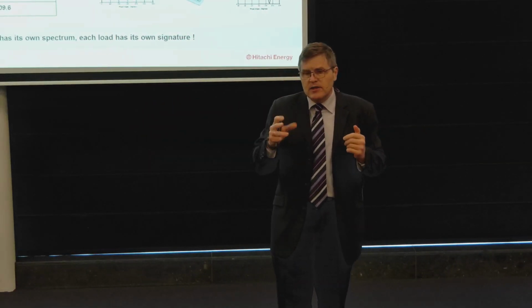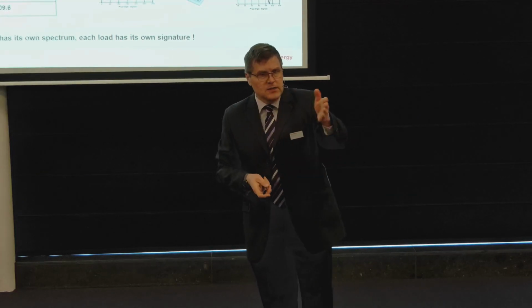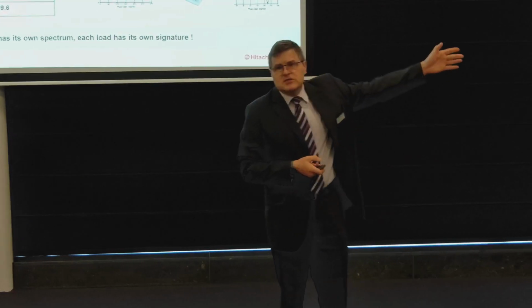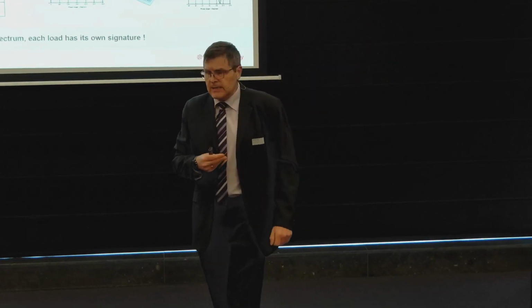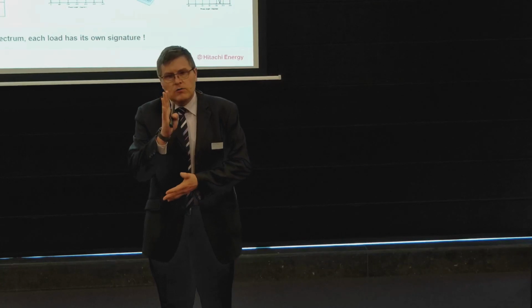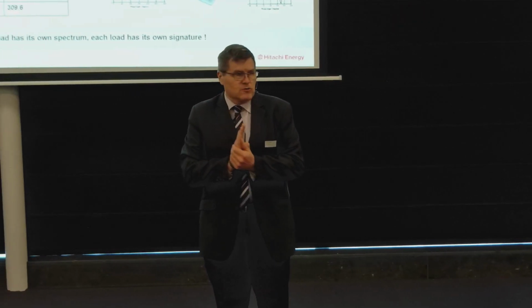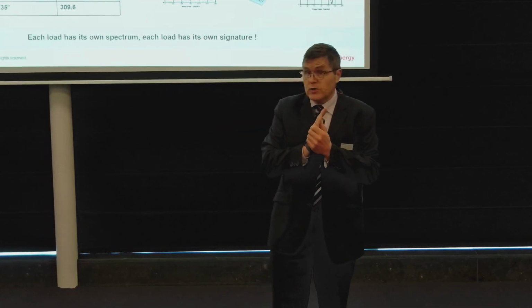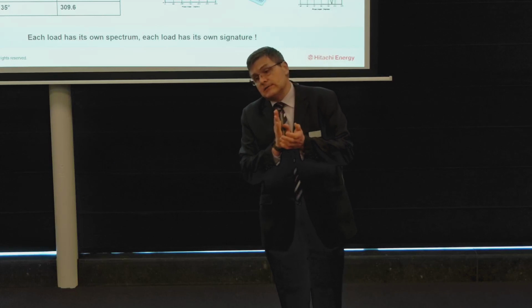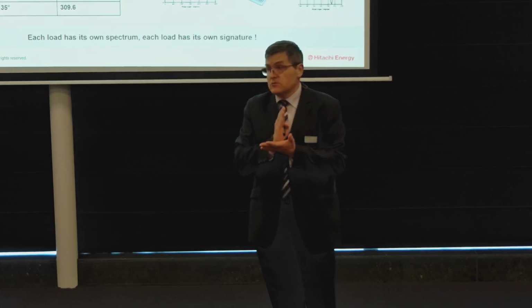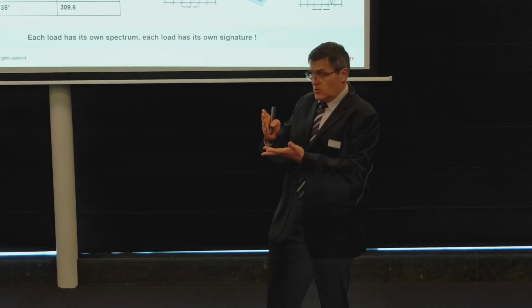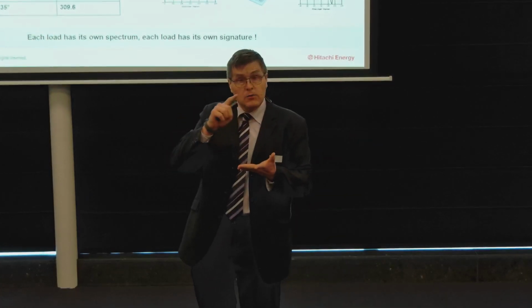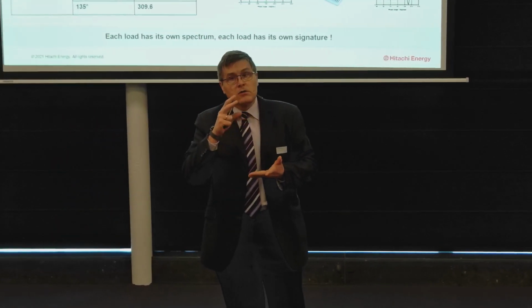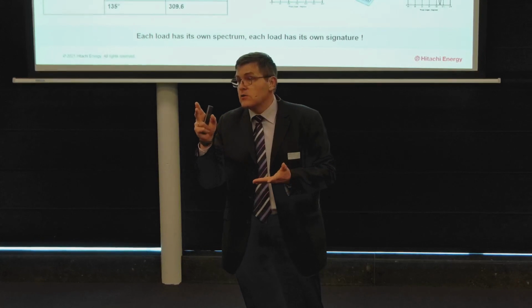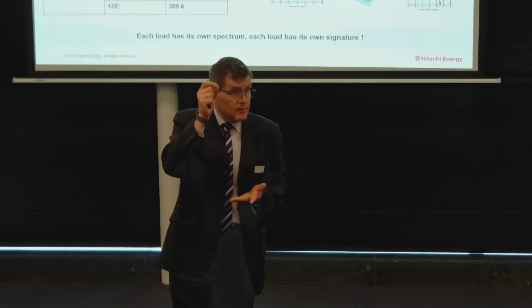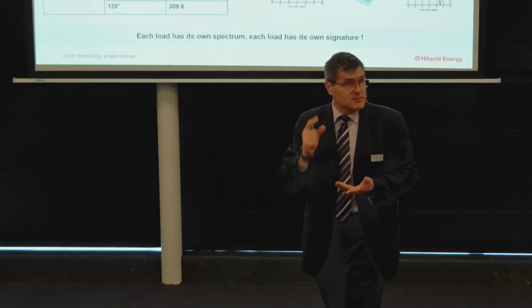So I take an example. If immunity is 12%, which is most of the levels given in the EMC standard, IEC 61000, that we have seen. So immunity is around 12%. But for most of the loads that you have in industry or at home, if you have more than 6-7% THDV, you start to have some problems. That means that you have misfiring, you have overheating, you have sound, because harmonic 9 or 10 is 450 hertz. It is purely the sound of music, and it is perfectly audible.